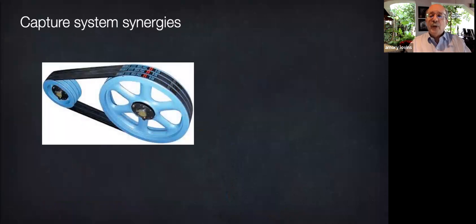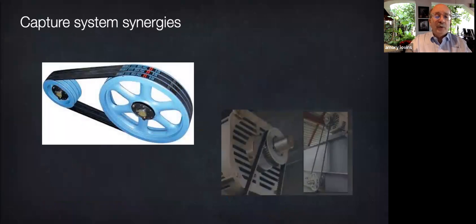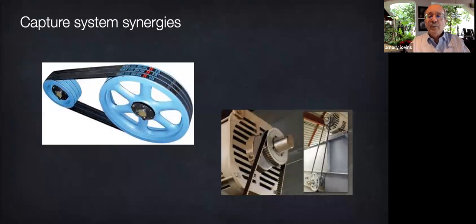For example, suppose you change a fan drive from traditional V-belts like this to a toothed, also called a cogged or synchronous belt. Well, that cuts the belt energy losses from 10 or 15+% to 1 or 2%. It makes the belt last much longer. It eliminates stretch and slip, and so you don't have to go maintain it all the time to retension the belt. There's almost no wear or tension adjustment. And because of those maintenance savings, each saved kilowatt hour costs about -$1.